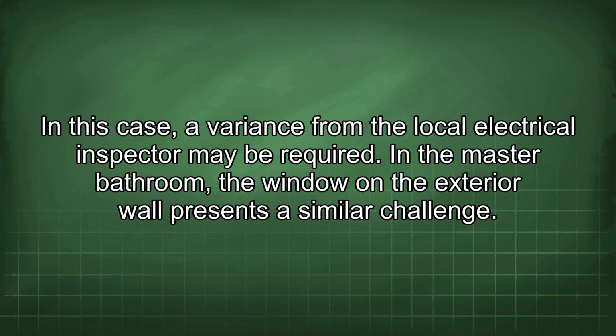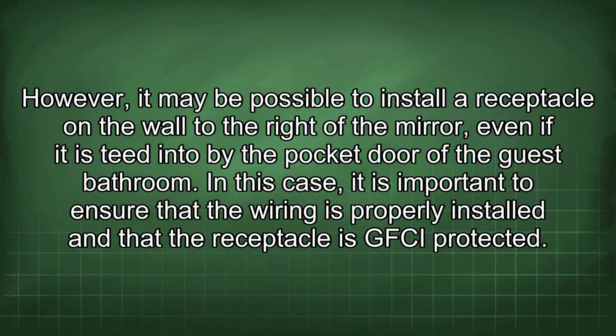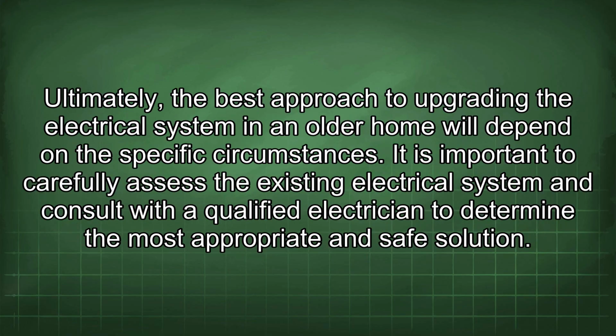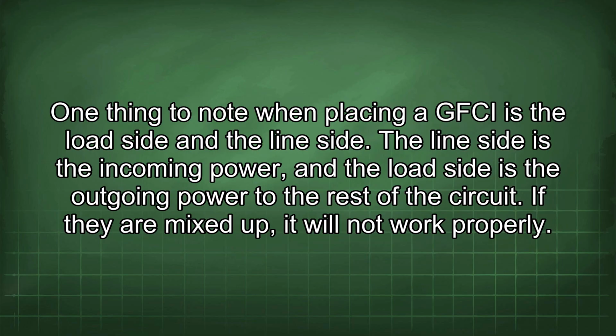In the master bathroom, the window on the exterior wall presents a similar challenge. However, it may be possible to install a receptacle on the wall to the right of the mirror, even if it is teed into by the pocket door of the guest bathroom. In this case, it is important to ensure that the wiring is properly installed and that the receptacle is GFCI protected. Ultimately, the best approach to upgrading the electrical system in an older home will depend on the specific circumstances. It is important to carefully assess the existing electrical system and consult with a qualified electrician to determine the most appropriate and safe solution. One thing to note when placing a GFCI is the load side and the line side.